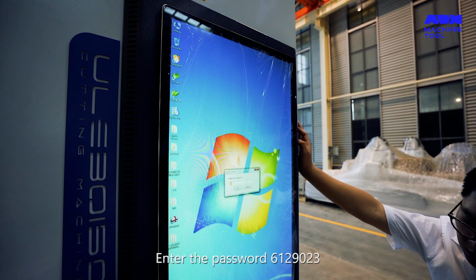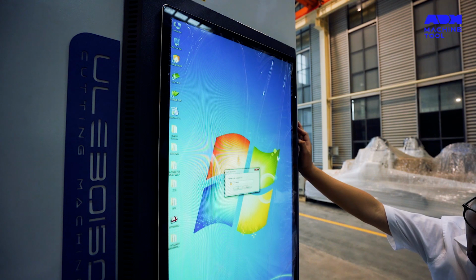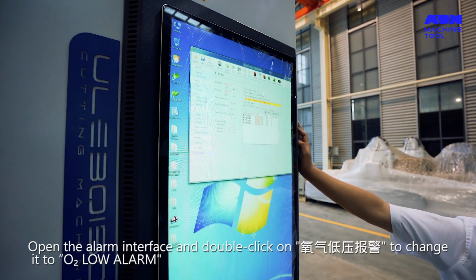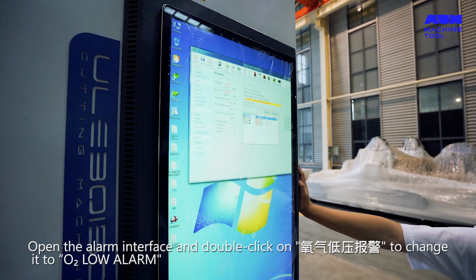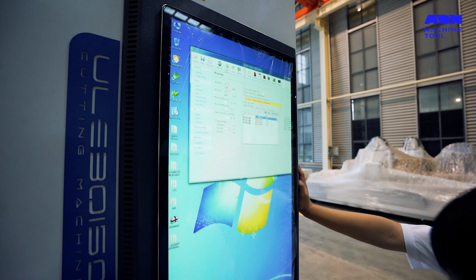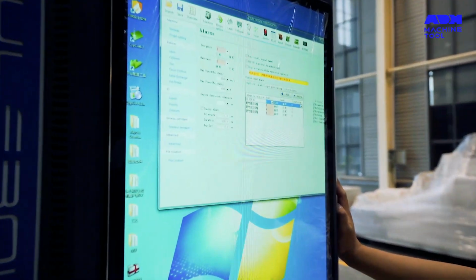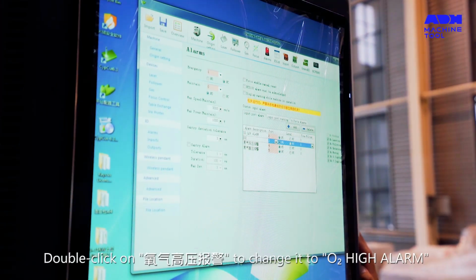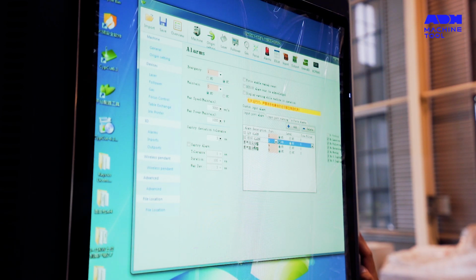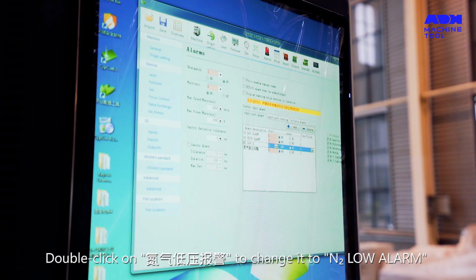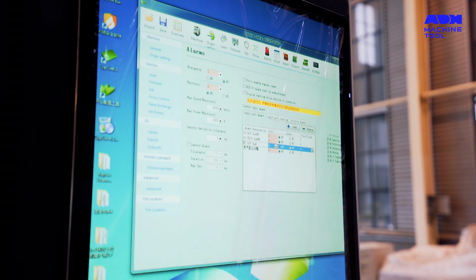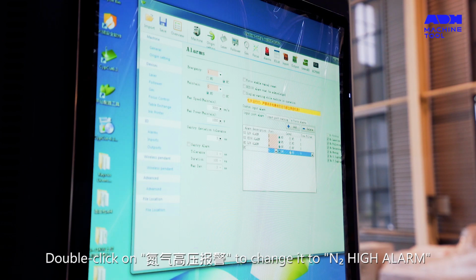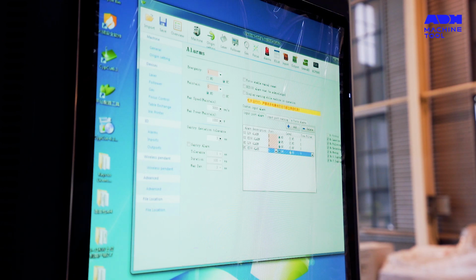Enter the password 6129023. Open the alarm interface and double-click on Yang Qi Dia Bao Jing to change it to O2 low alarm. Double-click on Yang Qi Gao Ya Bao Jing to change it to O2 high alarm. Double-click on Dan Qi Dia Bao Jing to change it to N2 low alarm. Double-click on Dan Qi Gao Ya Bao Jing to change it to N2 high alarm. Change the first and third lines to NC, then click Save and close the tool.